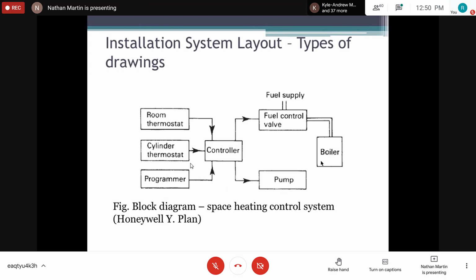I'm going to show you an example of a block diagram. This is really a temperature control system, a space heating control, where we show you the room thermostat. We are saying that the controller is the central unit, the brain, and it will take all of these signals in and control all of these other devices. So it takes in the signal from the room thermostat, from the cylinder thermostat, from the programmer, and it's used to control the pump, and shows you the flow out of the fuel control valve onto the boiler and so on. So it shows you the flow of the interconnection between the components.